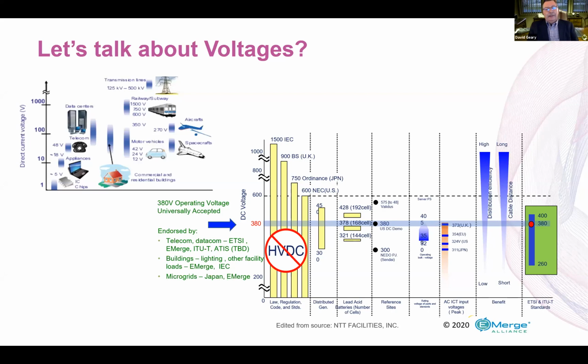We're already seeing different higher voltages, taking 380 volts and doubling it for larger scale microgrids. To be clear, this isn't high voltage DC, just higher voltage DC. We don't get to high voltage DC until we go above 1500 or 2000 volts. And then there's ultra high voltage DC, used in transmission, and it's actually being used quite extensively now.